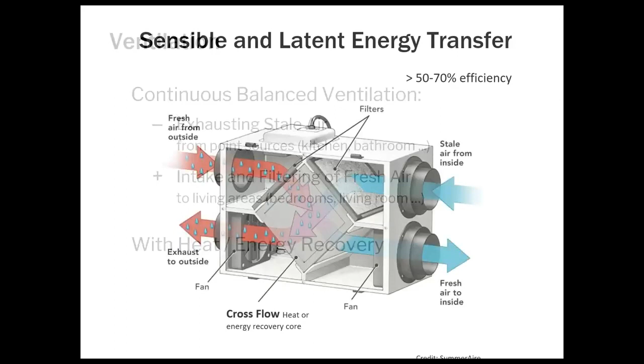There are a variety of different HRV and ERV equipment out there. This is a cross-flow type system that is commonly used at the apartment level. It has generally a low efficiency, and at that low efficiency is not commonly seen as ideal for passive house level performance. Very often our ERV is a critical part of a passing design for passive house certification. And so these simple cross-flow type ERVs don't always quite get there.